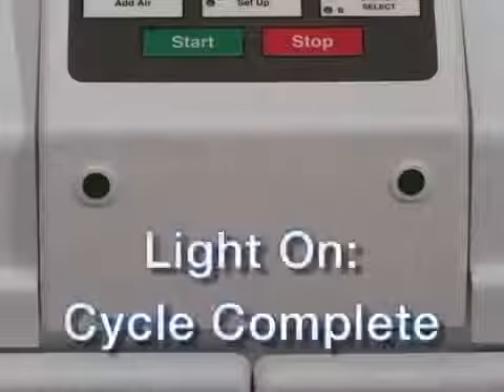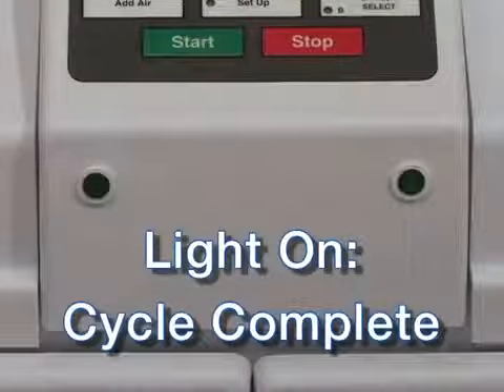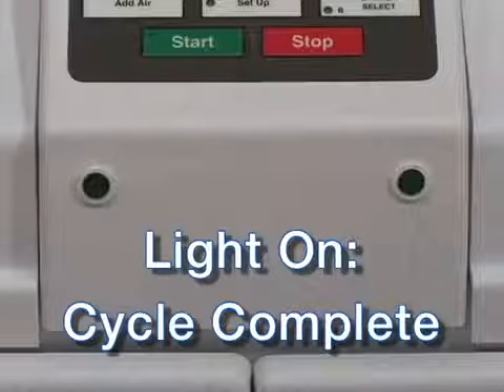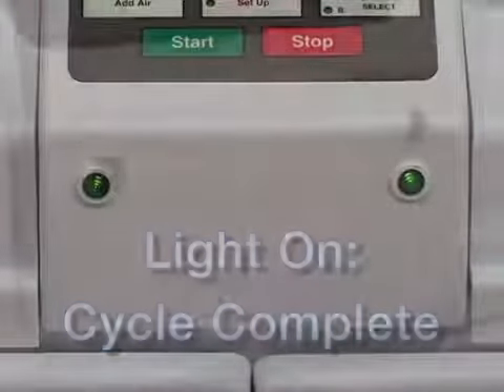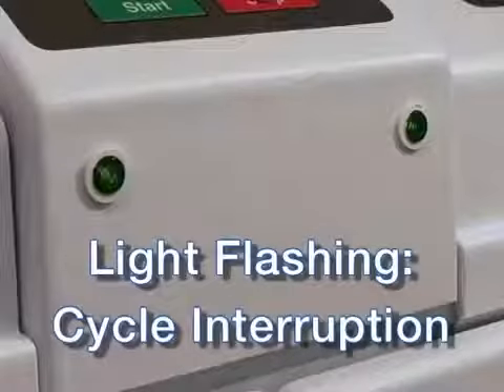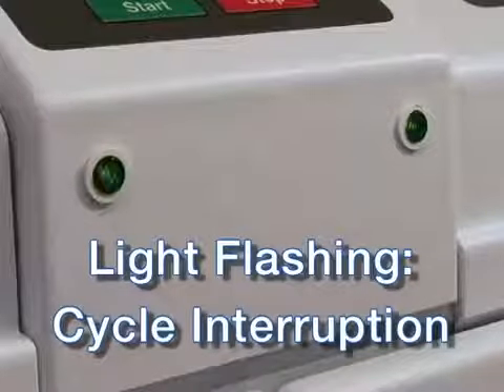The DSD-201 will dynamically print a record of the cycle, including the ID data, cycle complete message, any error messages, and basin temperature of the disinfectant. This function can be activated using the Setup function, which we will discuss later. When the disinfection process is complete, the process indicator light on the front panel will turn on. The indicator light will flash intermittently if there has been a cycle interruption.